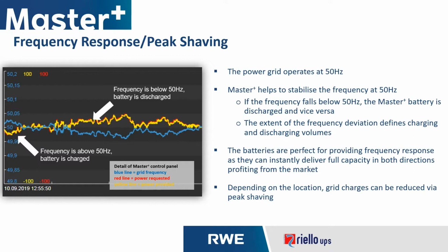So exactly how does the system operate? Well, if we look at the frequency response and the peak shaving aspect of the system, we know that the power grid operates typically at 50 Hz. However, that frequency is constantly changing. Now the Master Plus helps to stabilize the frequency at 50 Hz. Therefore, if the frequency falls below 50 Hz, then the Master Plus battery is discharged and vice versa. The extent of the frequency deviation defines the charging and discharging volumes of the system.